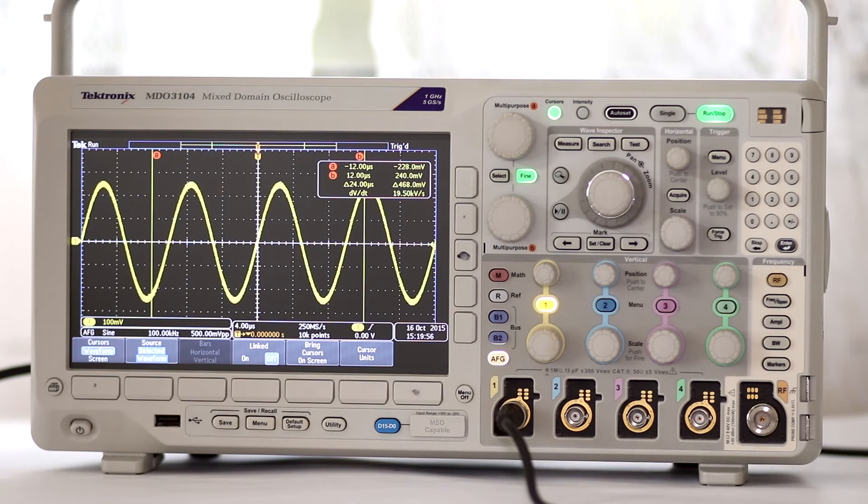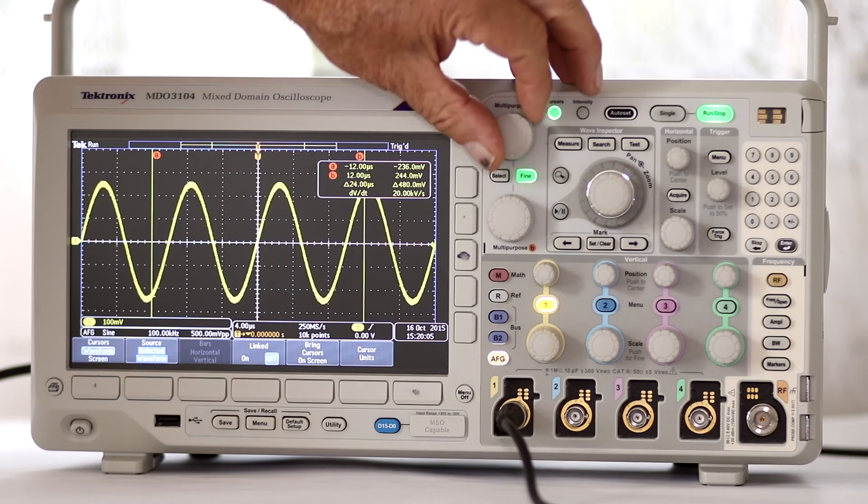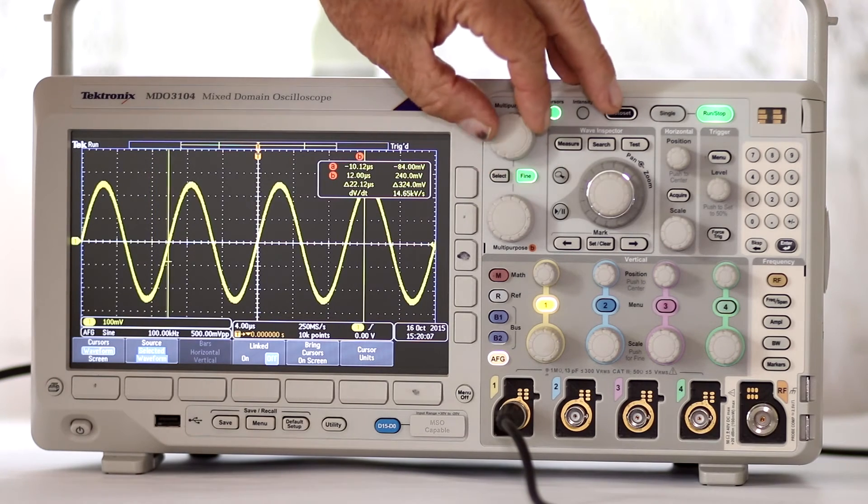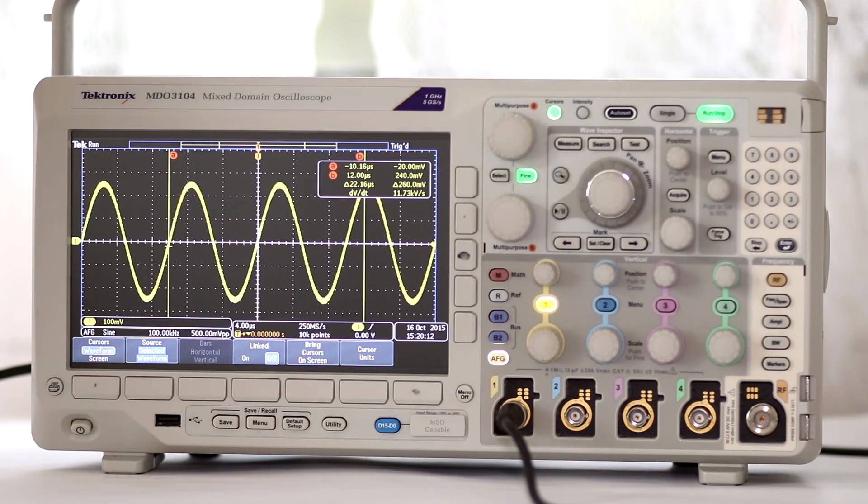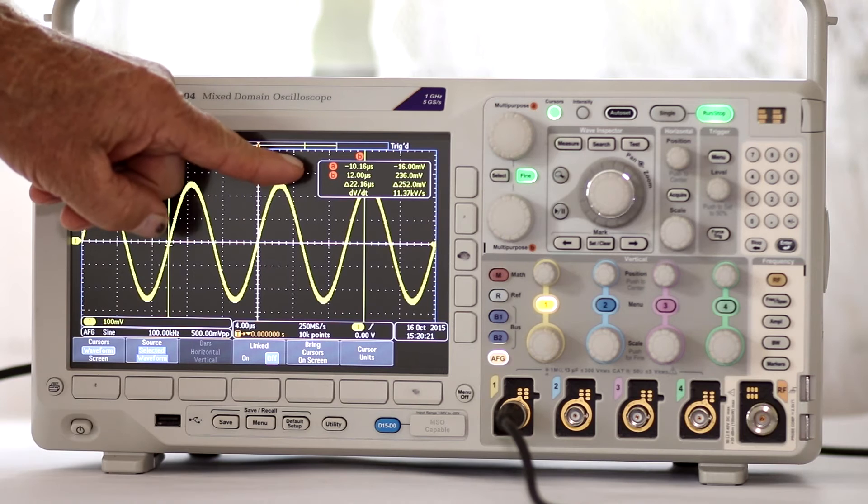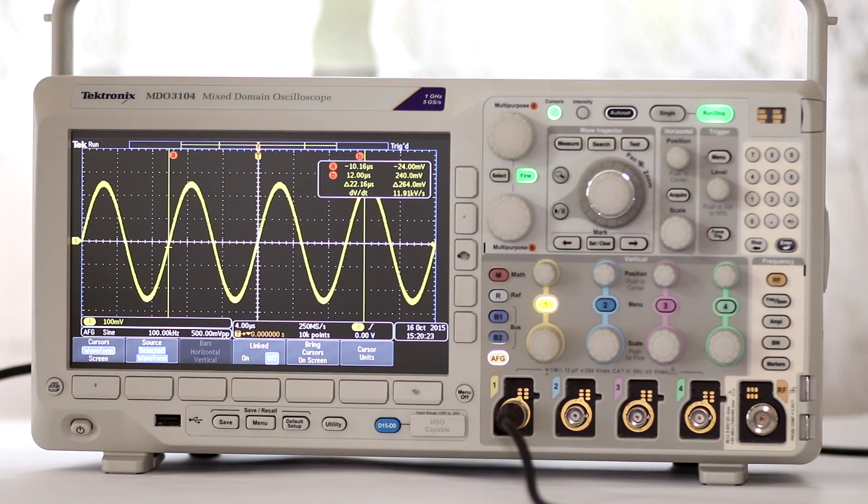Multipurpose knob A moves left cursor in either direction so that it intersects the x-axis at different points along the timeline. As you do this, appropriate values in the cursor readout at the top right of the display change. In the left column, labeled A, top line, the absolute value in microseconds changes.